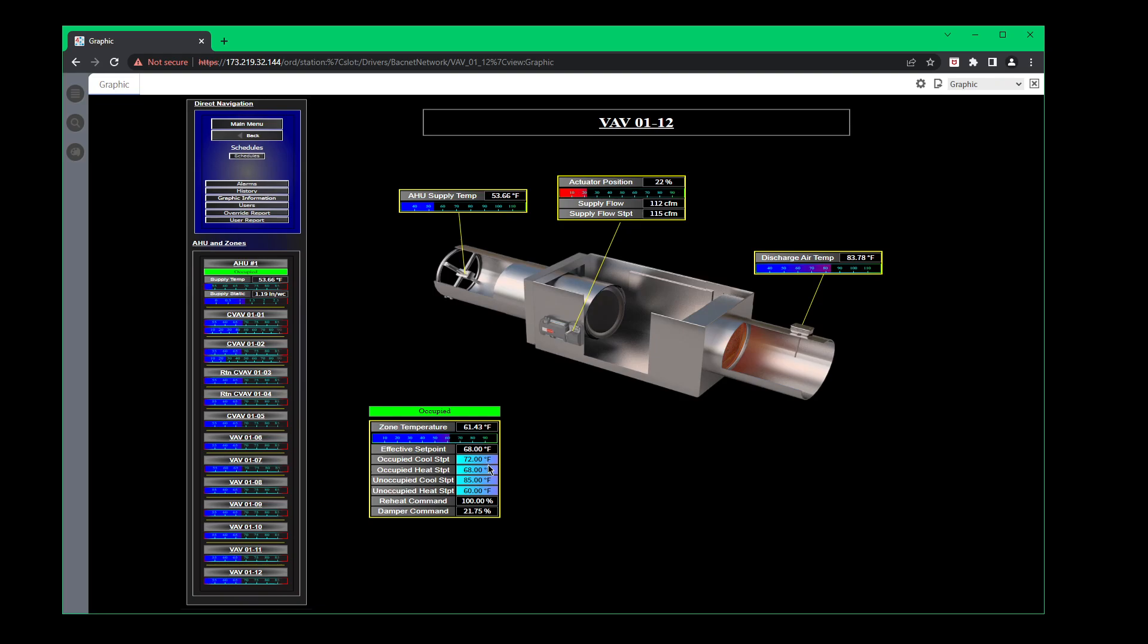Now, the biggest thing, your occupied heat and cool set point need to be two degrees differential minimum, meaning that it could be a higher span. I wouldn't suggest anything above a four degree span because if you start spanning out too much, then you're going to have a bunch of temperature fluctuations throughout your building. And you're going to have a lot of nuisance issues.